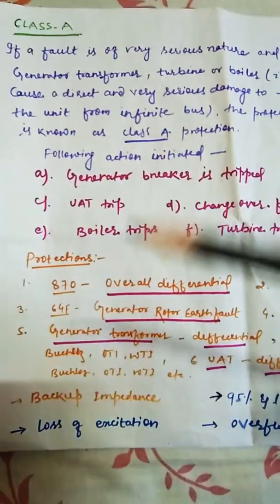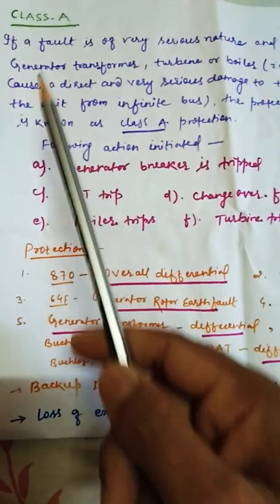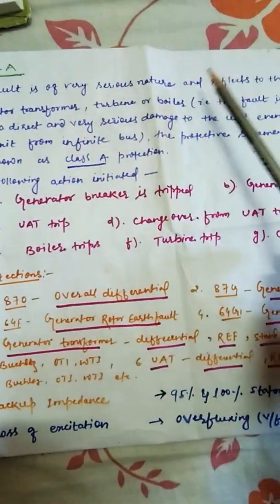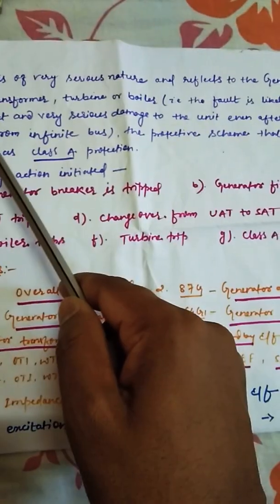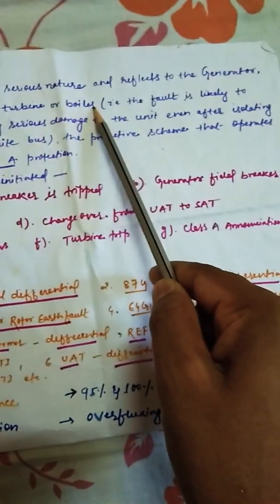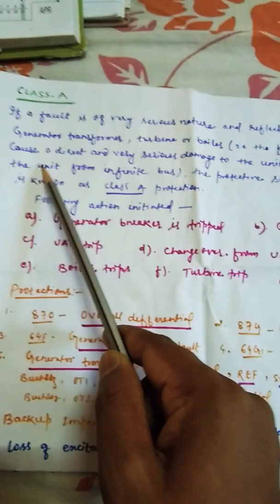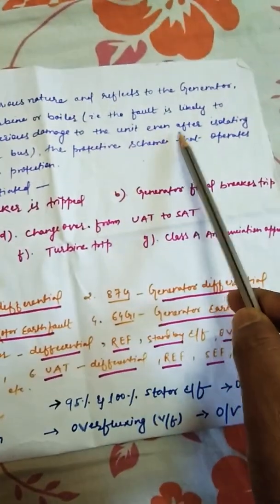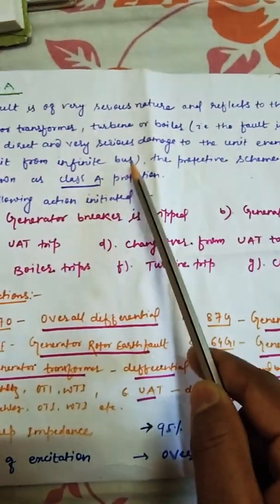Class A, Class B, and Class C. If a fault is of a very serious nature and directly affects the generator, generator transformer, turbine, or boilers — that is, the fault is likely to cause direct and very serious damage to the unit even after isolating the unit from the infinite bus — the protection scheme that operates is known as Class A protection.